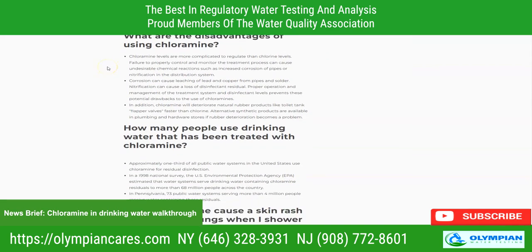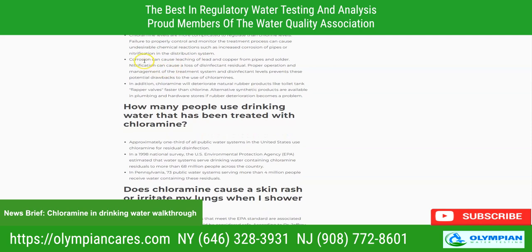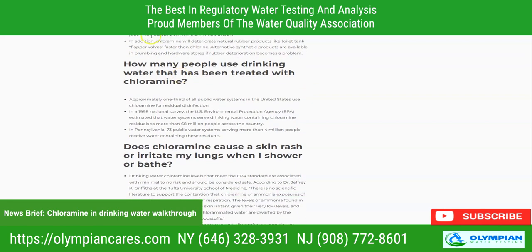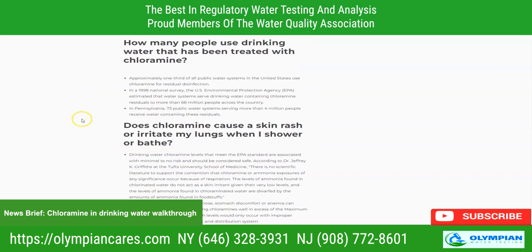But there are disadvantages. What are the disadvantages? Chloramine levels are more complicated to regulate than chlorine levels, and failure to properly control and monitor the treatment process can cause undesirable chemical reactions, such as increased corrosion of pipes or nitrification. It can cause the leaching of lead and copper from pipes and solder, and it can cause a loss of disinfectant residual, so proper operation and management of treatment systems is needed. In addition, chloramine will deteriorate natural rubber products like toilet tank flapper valves faster than chlorine.